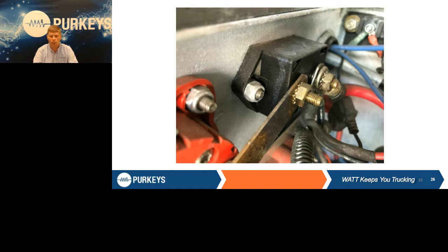Excessive current is going to generate more heat, and that's what a breaker relies on to trip. This one was tripping because these two studs had loose nuts on them. So it was creating a lot of extra heat because of that resistance going into that circuit breaker and causing it to trip. We went back through, just like Thomas mentioned earlier, checked the stack up, made sure everything was on there in the right order, big cables first, smaller wires or cables afterwards, tightened everything up, and that problem went away. But it was amazing, they equated it to a faulty charging system or faulty batteries as why it was tripping.